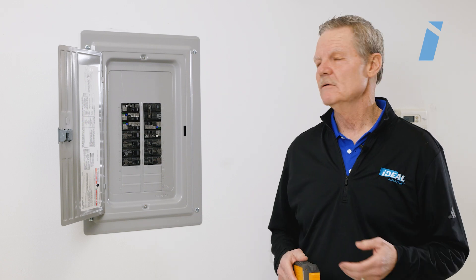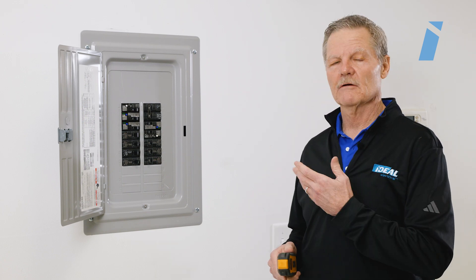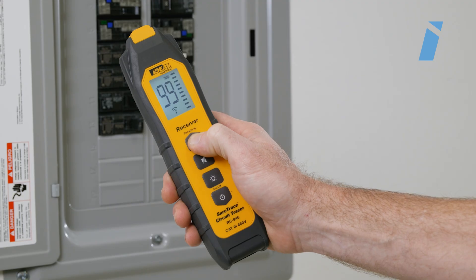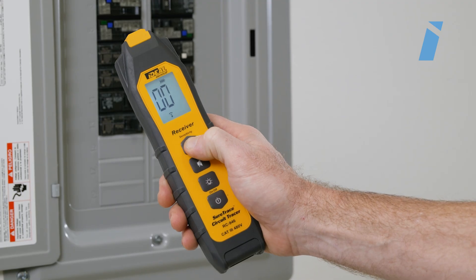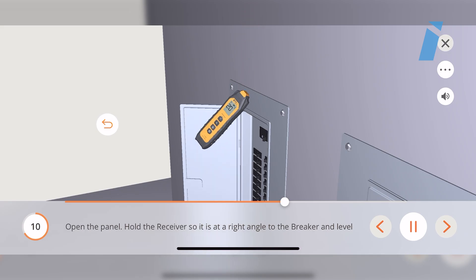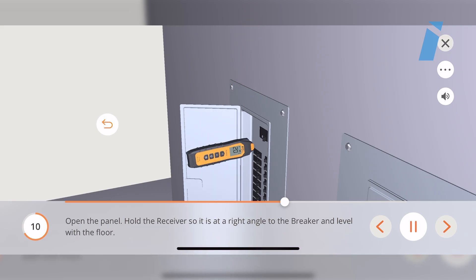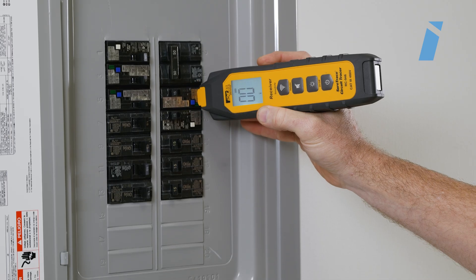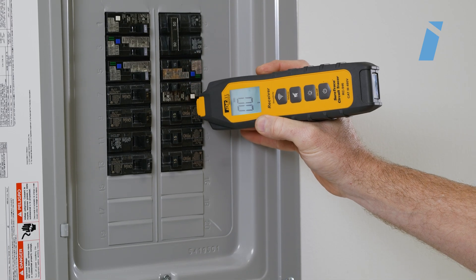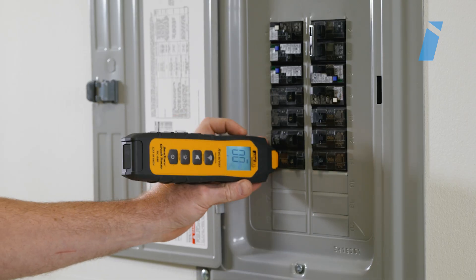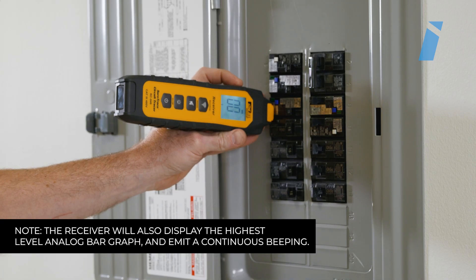Once you've identified the panel, open it up and set the receiver to the lowest setting, which is level one. Then place the receiver on the panel positioned 90 degrees to the breaker, with the flat tip of the receiver placed flat on the outside portion of the breaker. Scan the entire panel in a racetrack pattern with the receiver in this position to identify the breaker with the highest signal strength displayed on the receiver.